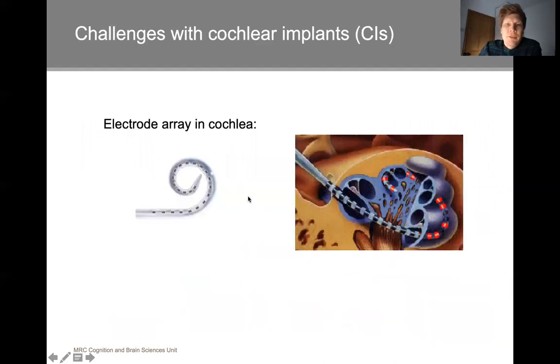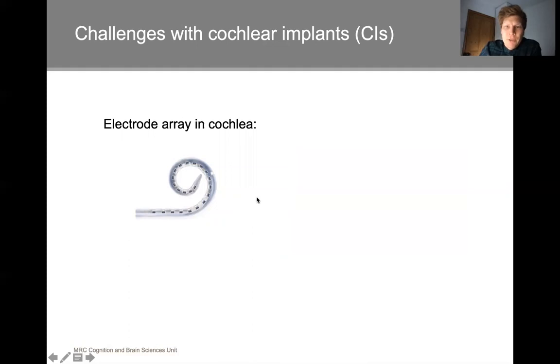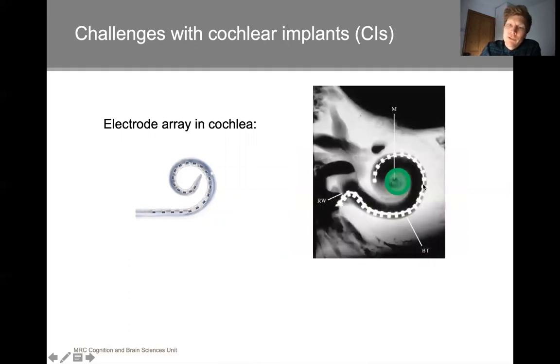And there are quite a few challenges that apply to cochlear implants, because as good as this may sound in theory, in practice, as usual, there are some limitations. When you imagine having this electrode array inserted into the cochlea, and you stimulate at one contact here, for example, then the current would ideally just be exciting the neurons that are closest to that contact. So that when you then activate a different contact in order to stimulate, for example, a speech signal, or a speech signal in background noise, or a music signal, you could differentiate these different frequency bands from each other. But unfortunately, electrical current flows in every direction, and you have a lot of spread or overlap between these different channels, and that effectively reduces the spectral resolution that cochlear implants can deliver.